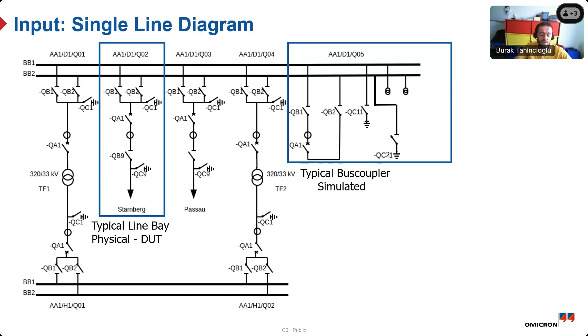And here on the specification phase, we will define the functions that the line bay will take over. And then we will have many boxes in most cases. That could be a merging unit with the substation control unit or switchgear control unit here, and communicating, so it's wired with copper cables to the switchgears in the switchyard, and then communicating out GOOSE and sampled values up to the IEDs in the control room for protection and control.